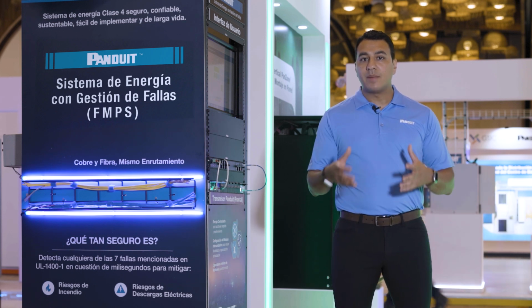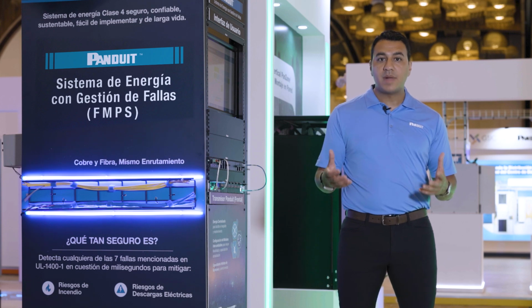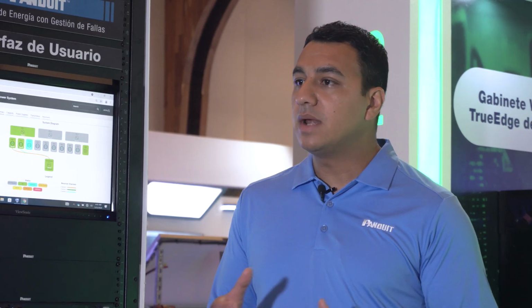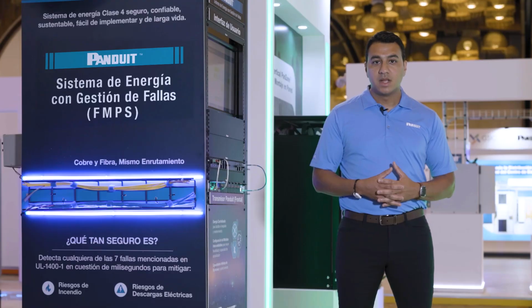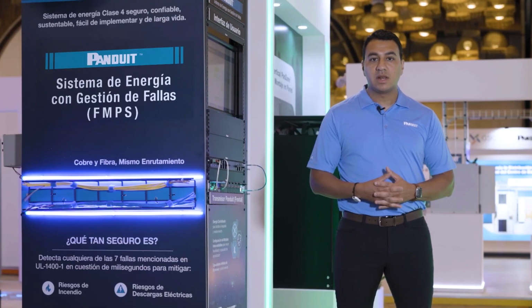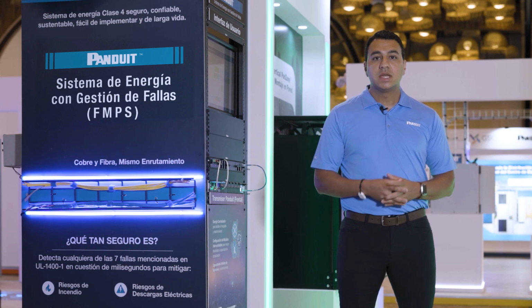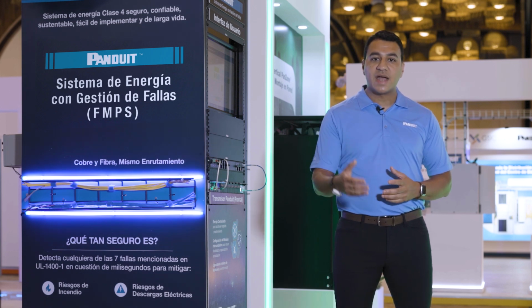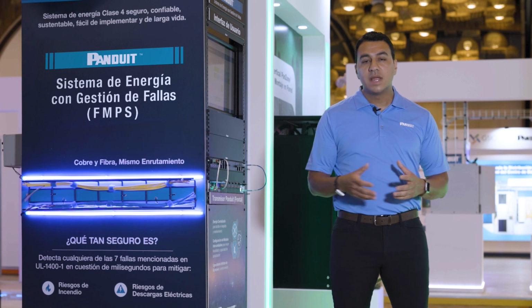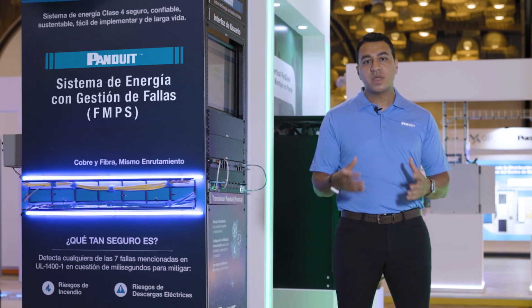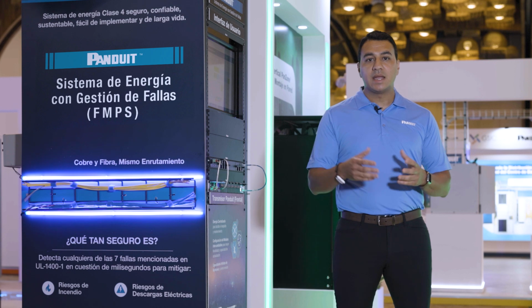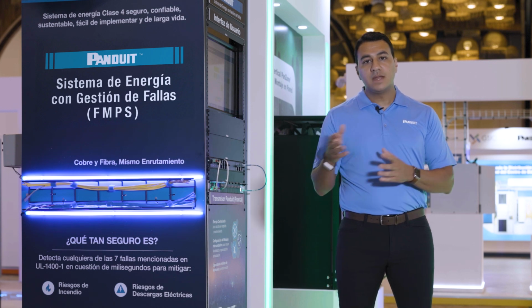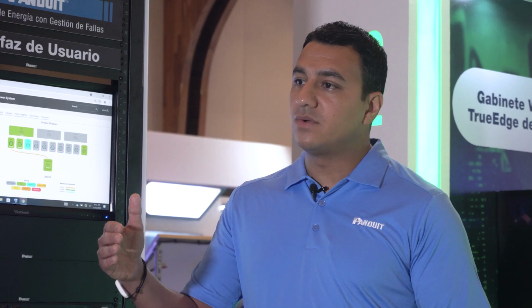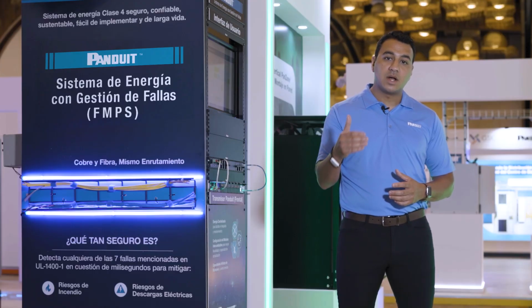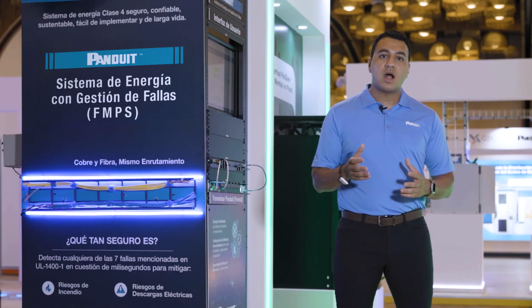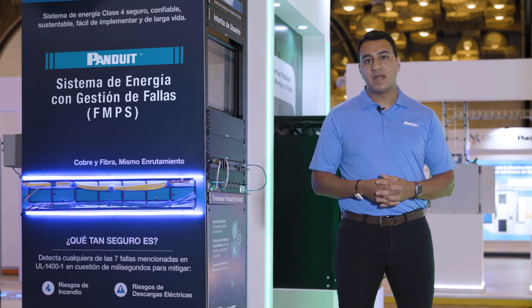The most common application of Class 2 is PoE, Power over Ethernet, where power in PoE is considered Class 2. The nice thing about it, because it can be installed by low voltage technicians, it doesn't have to be running in conduit, so it's fast and easy to deploy. However, it can't really go far. As you may know, PoE is limited to only 100 watts and only 100 meters. Then we have Class 3, limited to 100 watts and 150 volts, not very commonly used, mainly for home theater and sound system applications.